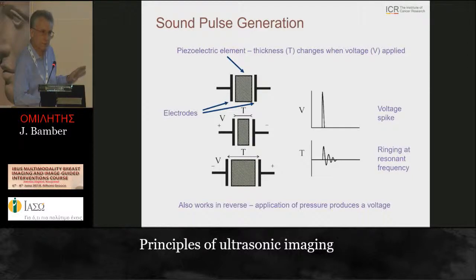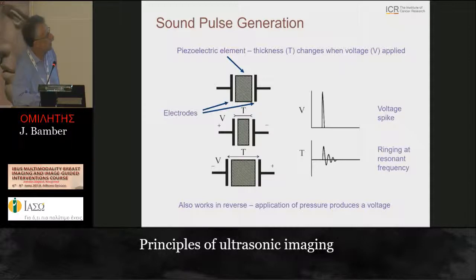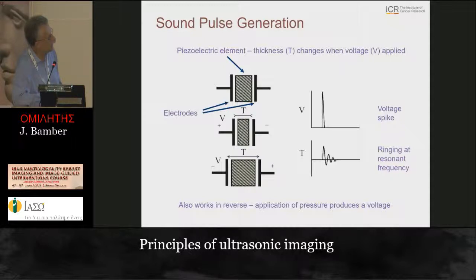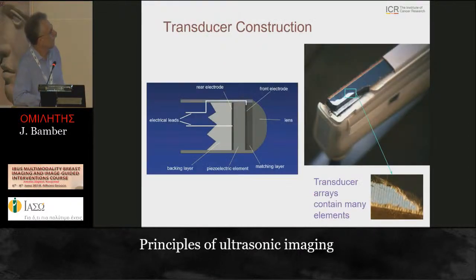How do we generate those sound pulses? It's done with a piezoelectric transducer. Piezoelectric means that if we apply a voltage across a crystal, it will change its thickness. That change in thickness, done rapidly enough, means we can expand and compress the adjacent tissue, or contract it and decrease the pressure. Applying a voltage spike causes it to oscillate in thickness, so the pressure adjacent in the tissue does the same, and that pressure wave then travels into the body.